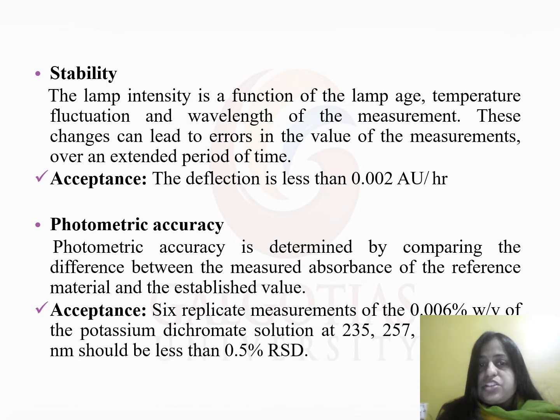Stability: the lamp intensity is a function of lamp age, temperature fluctuation and wavelength of the measurement. These changes can lead to error in the value of the measurement over an extended period of time. Acceptance: the deflection is less than 0.002 AU per hour. Photometric accuracy is determined by comparing the difference between the measured absorbance of the reference material and the established value. Acceptance: 6 replicate measurements of 0.006% weight by volume of the potassium dichromate solution at 235 and 257 nanometer should be less than 0.5% RSD.